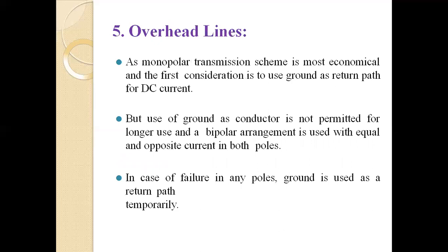Next part is the overhead lines. As the monopolar transmission scheme is the most economical, the first consideration is to use ground as a return path for the DC current. But use of ground as a conductor is not permitted for long-term use, and a bipolar arrangement is used with equal and opposite current in both poles. In case of failure in any pole, ground is used as a return path temporarily.